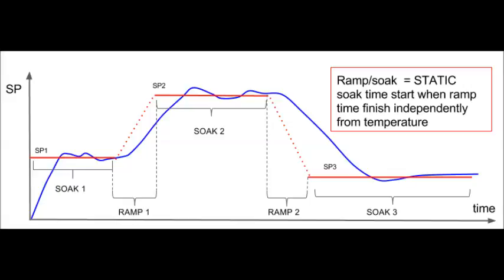There are two implementations of this algorithm called static and dynamic. In the static execution, the soak time starts when the ramp time finishes, and this is independent from the current temperature. As you can see in the graph, here you have two setpoints — SP1 and SP2 — and two soak times. Soak time 2 starts independently from the temperature when the ramp ends.